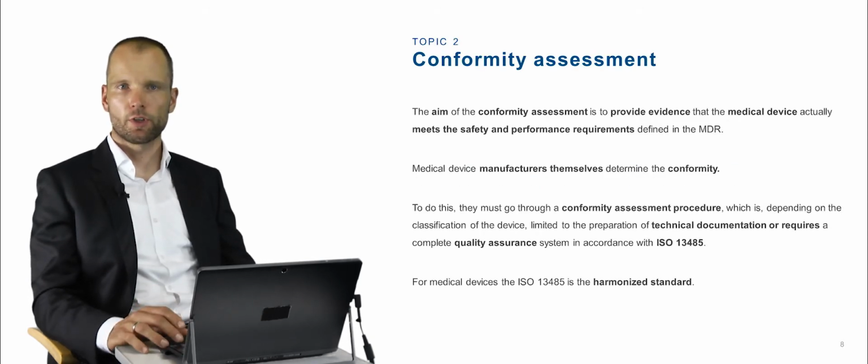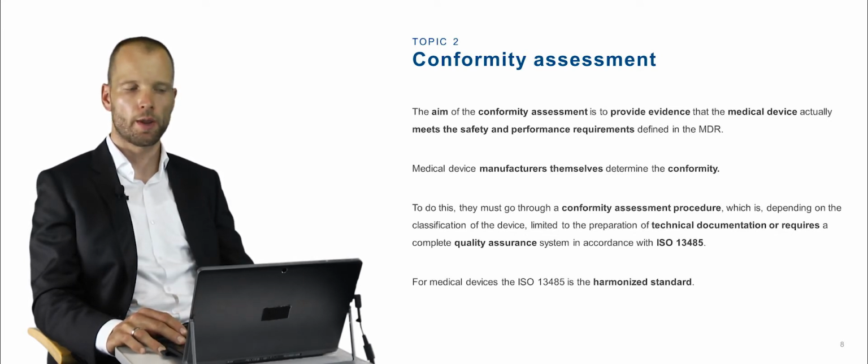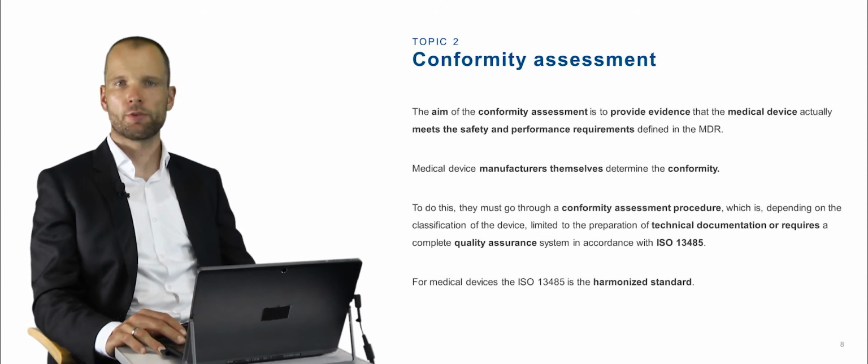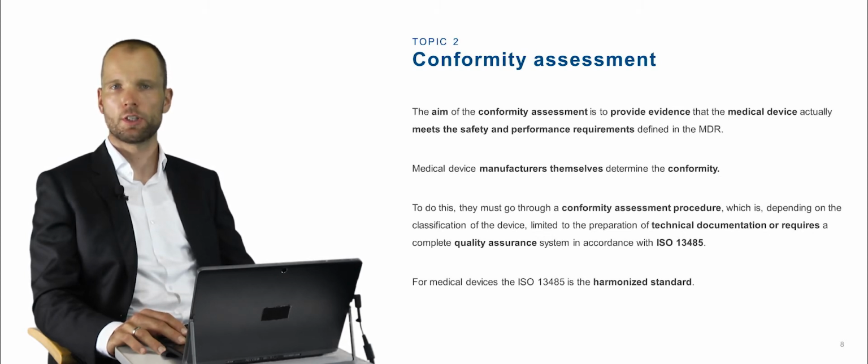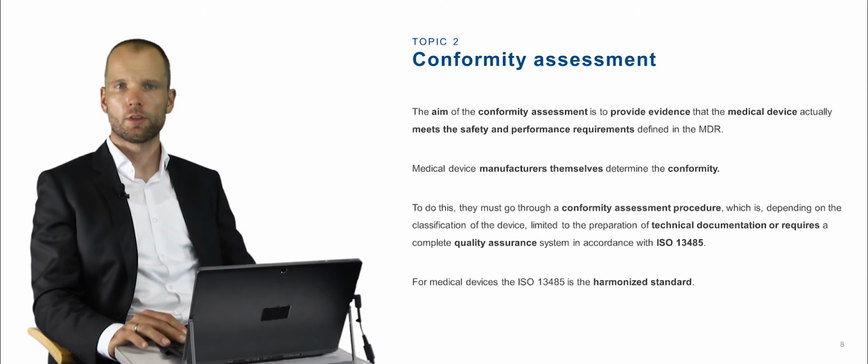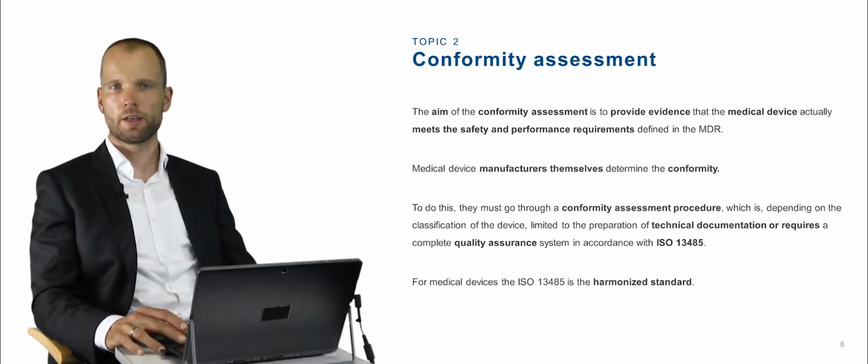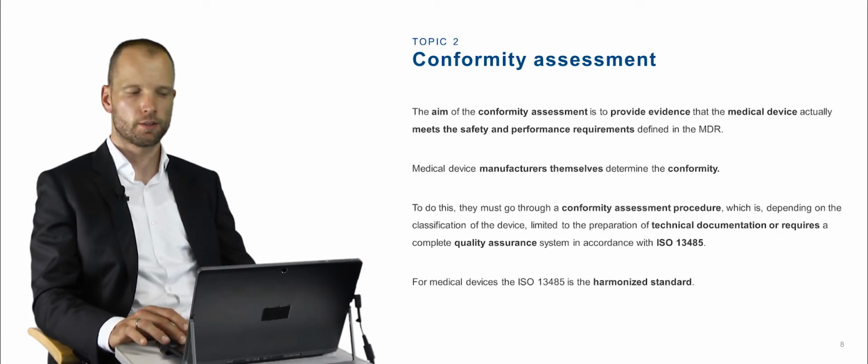Let's talk about the conformity assessment. The aim of the conformity assessment is to provide evidence that the medical device actually meets the safety and performance requirements, which are defined in the medical device regulation. Medical device manufacturers themselves determine the conformity. To do this, they must go through the conformity assessment procedure, which depends on the classification of the device. It is limited to the preparation of the technical documentation or requires a complete quality assurance system in accordance with ISO 13485. For medical devices, ISO 13485 is the harmonized standard.